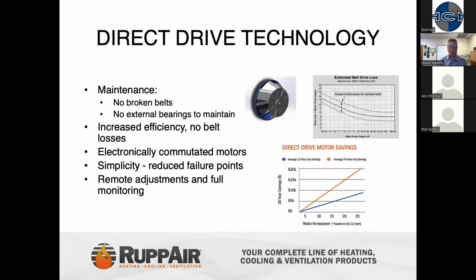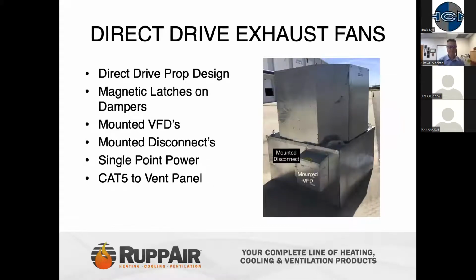Make sure if you're utilizing these exhaust fans and even the makeup airs that you're utilizing the newest technology. Direct drive technology is a big part of what we see every day now. So have these in place, everything on the smaller side, and make sure you have ECM motors in place. Remote adjustment and full monitoring for these fan products. So big benefits on the direct drive fans.